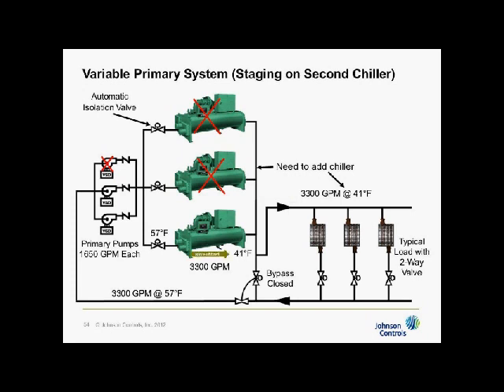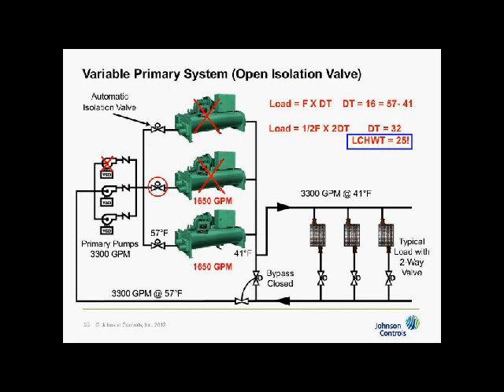Whatever the reason is that you now need to add another chiller, the very first thing that I have to do is open the isolation valve of the chiller I want to add. Now, a moment ago, down here with this chiller, I had 3,300 GPM. I open a two-position valve that might take 10 seconds to open, maybe 15, and all of a sudden I've halved the flow in this chiller down here. This chiller has inlet vanes inside of it that take 2 minutes to close, to go from 100% open, where they were a moment ago at full load. It wants to go to 50% load because it's sharing the load with the other chiller.